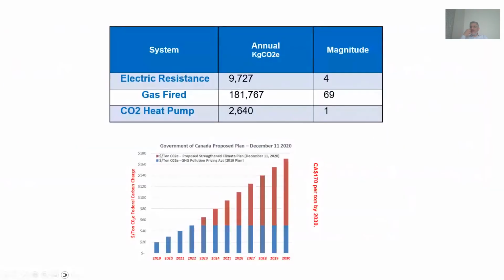Again, if we consider electric heater, gas-fired boiler, and CO2 heat pump, you have a substantial reduction in CO2 emission compared to gas-fired. That is obvious because we are running a lot of gas there. But even compared to electric heating, which is a 1:4 magnitude, it shows that it's a 4 COP on our side.